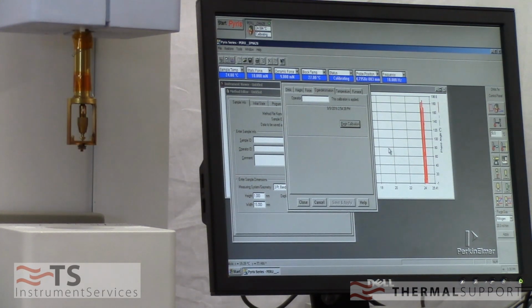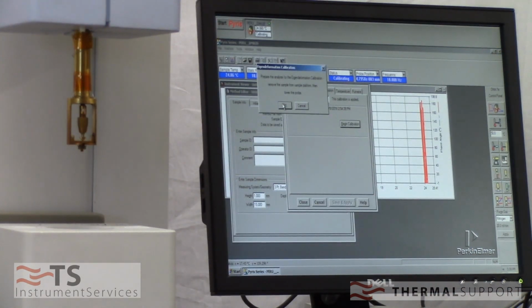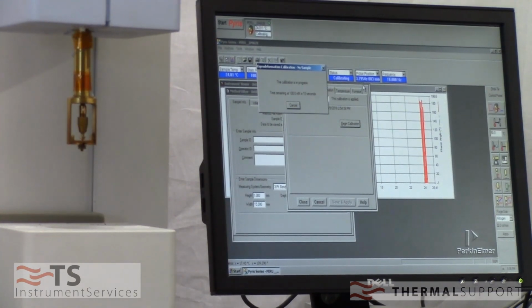So to start that with it at 0, we're going to say begin cal, click OK, calibration in progress. It starts out at 100 millinewtons. It's going to be there for 25 seconds. And we're going to be patient. We're going to sit back for it to finish that. And then I'll go to another portion. I'll tell you as it goes through that.